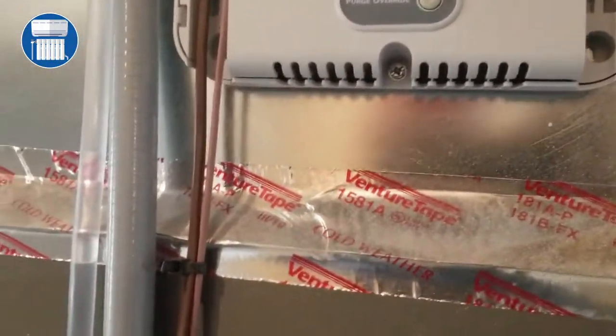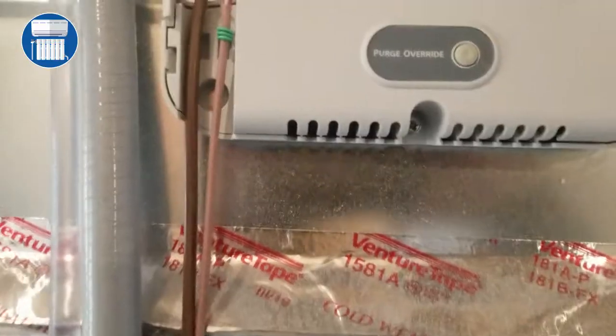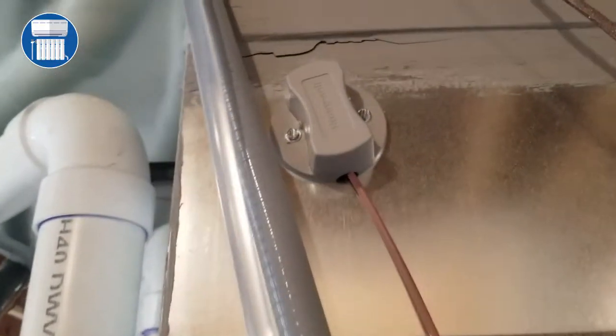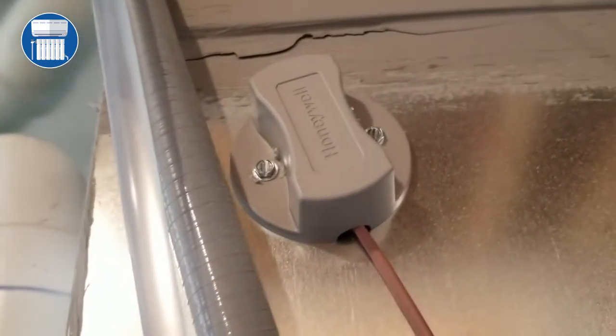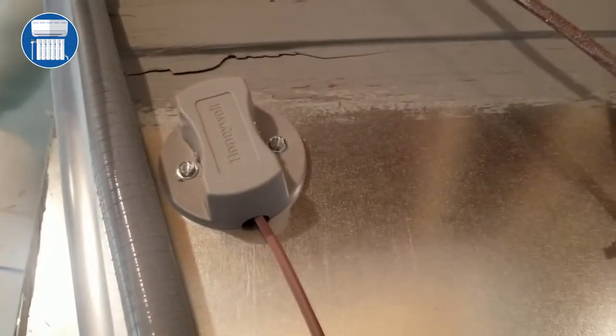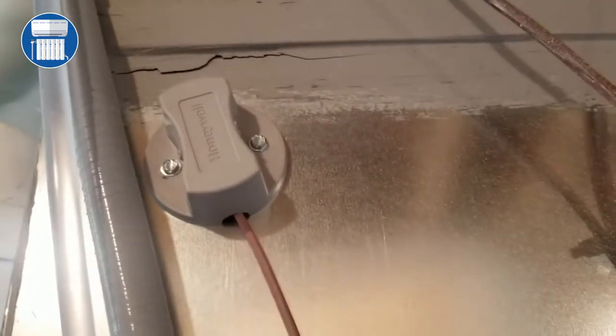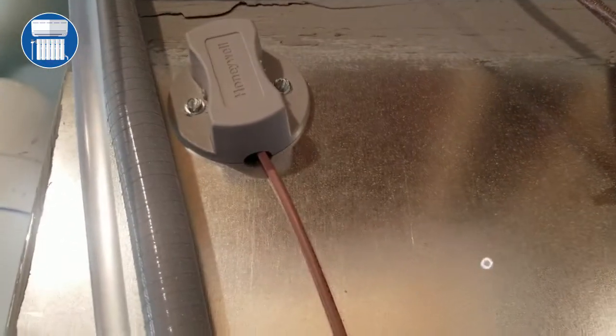Let's look at our wires. First wire, we have a sensor here that goes all the way up. Sometimes it's needed, sometimes you don't need it. What happens if it's a low pressure sensor? If the temperature of the coil is too cold, it will cut off the system.